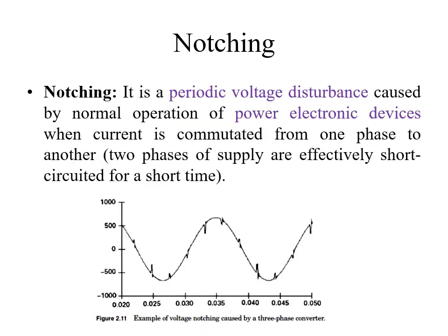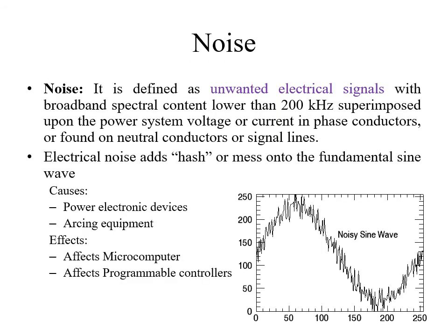Notching occurs when periodic voltage disturbances appear at regular intervals — you can see notches at particular equal intervals of time. This type of disturbance is called notching and normally occurs due to commutation from one phase to another. Noise refers to all other unwanted electrical signals that cause disturbance to the sine wave — any sine wave distortion other than DC offset, harmonics, interharmonics, and notching is called noise. It may be caused by power electronic devices and arcing equipment.